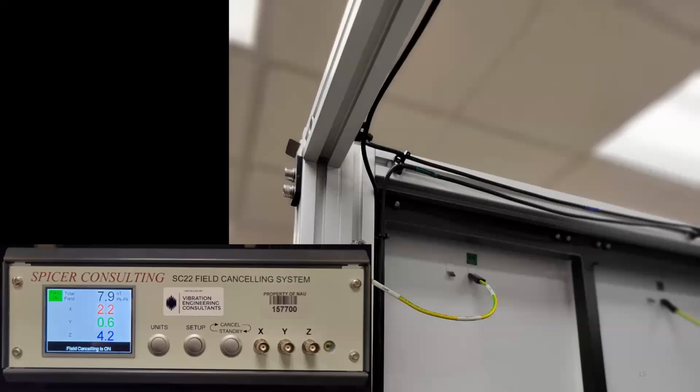But we also have a magnetic field cancellation system. So that's this guy right here. It controls these loops. There's 7 different loops, 1 on each face and then 1 in the center. And what that does is there's sensors as well. I think in one of the previous images you can see it. There's these little green boxes that sit inside. There's 2 of them. And they sense magnetic fields, and then we actively cancel them with these loops. And right now the cancellation is on.